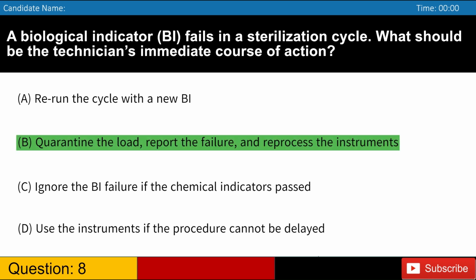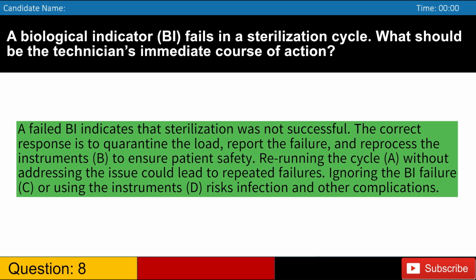Answer: B. A failed BI indicates that sterilization was not successful. The correct response is to quarantine the load, report the failure, and reprocess the instruments, B, to ensure patient safety. Rerunning the cycle, A, without addressing the issue could lead to repeated failures. Ignoring the BI failure, C, or using the instruments, D, risks infection and other complications.